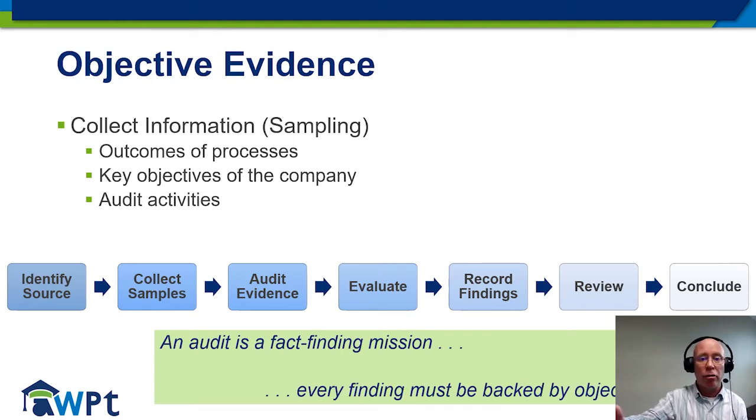And as an internal auditor, you are going to audit against those source documents. You will collect samples, whatever those might be. I'm going to witness that all of the uncertainty documents are based on ILAC P14. Okay? And so you will collect evidence, measurement uncertainty budgets, to make sure that all the components from ILAC P14 are being met. You will evaluate those budgets against the criteria, and you'll record the findings.